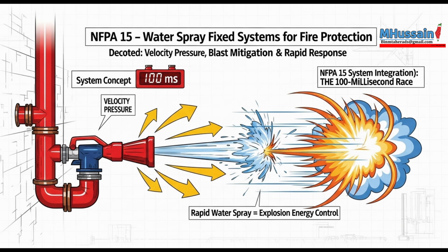All right, we've ensured the components are tough enough. Now, the next big step in the standard: defining the goal. How much water, precisely where, to meet the objective. Let's start with exposure protection for uninsulated vessels in 7.4 and that fundamental thermal load calculation. The standard sets a minimum application rate, not less than 0.25 gallons per minute per square foot (GPM/ft²) of the exposed surface area.